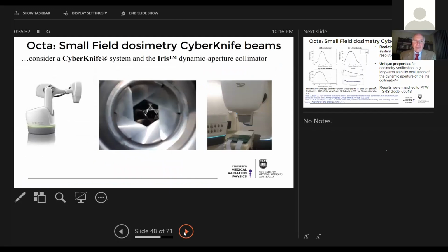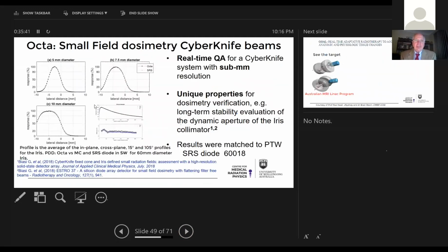So it's very useful for verification in CyberKnife, particularly the iris collimator, which I would like to show you. You can see on this picture the 5 millimeter diameter and 7.5 millimeter diameter profiles provided by the iris collimator. And you can see the comparison on the right side with the SRS diode from PTW, which is sort of the gold standard for such kind of profile verification. And again, we're getting beautiful agreement, but we don't need to use point-by-point scanning in a water tank. We're using this immediately.